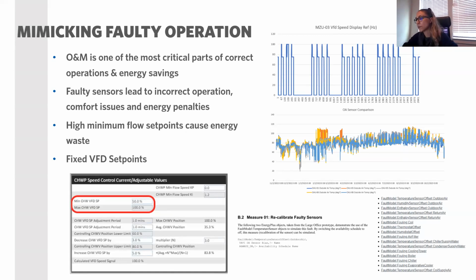The other part is, we see this a lot with the VFDs. When you add a VFD, you assume that it's going to modulate and you're going to save energy, but we mostly see they're actually locked to a certain speed. They're not really utilizing the capabilities of the VFD. So we can see this operation, and we can mimic this in an energy model. Or with minimum flow speeds, like on a chilled water pump or a hot water pump, the minimum speeds are actually fixed at like 50%. So you're not actually giving much room to save energy on the pump.